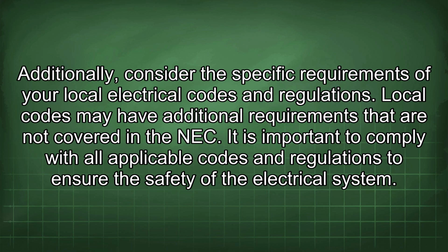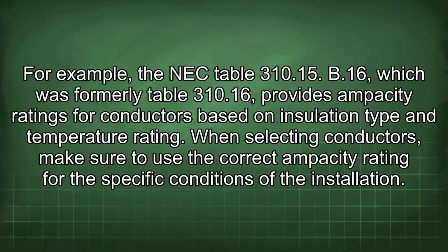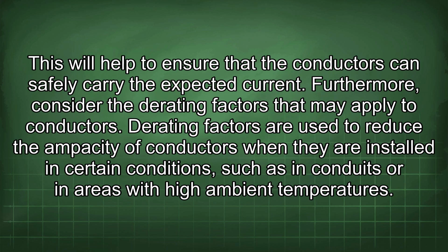Additionally, consider the specific requirements of your local electrical codes and regulations. Local codes may have additional requirements that are not covered in the NEC. It is important to comply with all applicable codes and regulations to ensure the safety of the electrical system. For example, the NEC Table 310.15(B)(16), which was formerly Table 310.16, provides ampacity ratings for conductors based on insulation type and temperature rating. When selecting conductors, make sure to use the correct ampacity rating for the specific conditions of the installation. This will help to ensure that the conductors can safely carry the expected current.